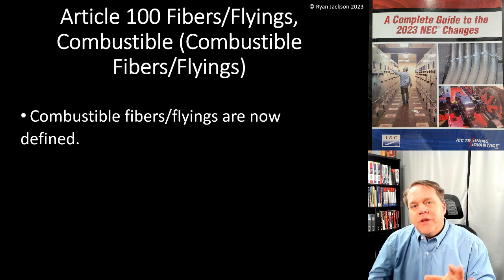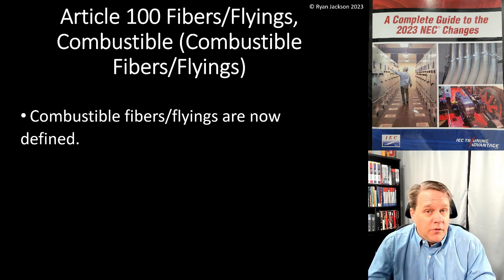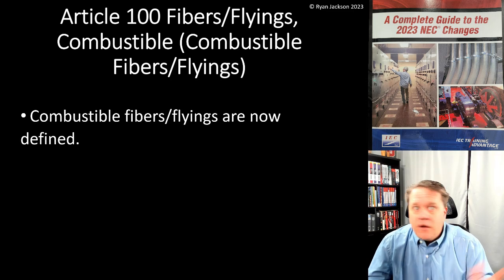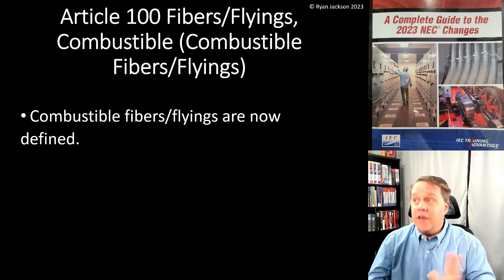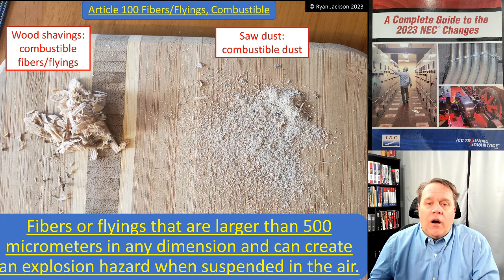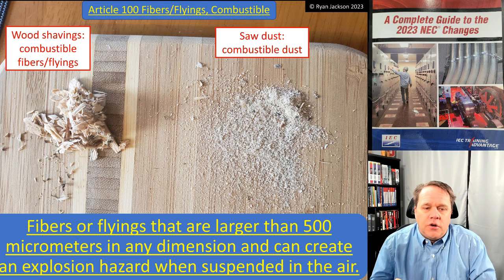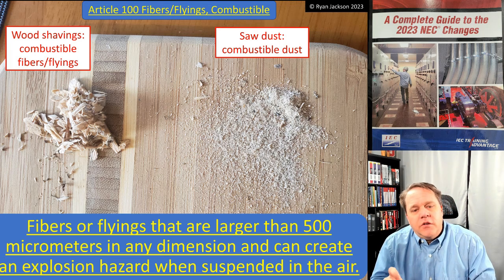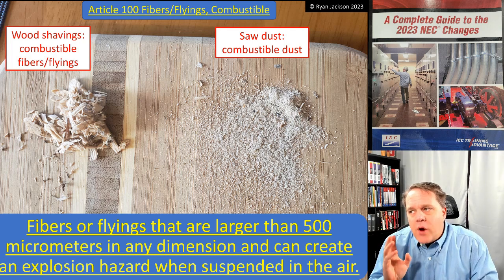Article 503 Class 3 locations are for ignitable or combustible fibers and flyings. Previously, the NEC never defined that term, which was patently ridiculous — but now we do have definitions. A combustible fiber or flying is a fiber or flying larger than 500 micrometers in any dimension that can create an explosion hazard when suspended in the air.